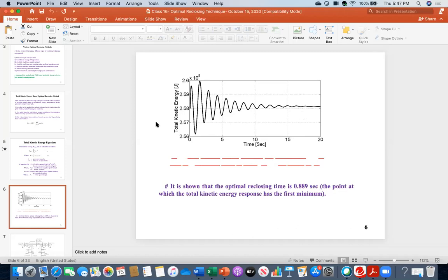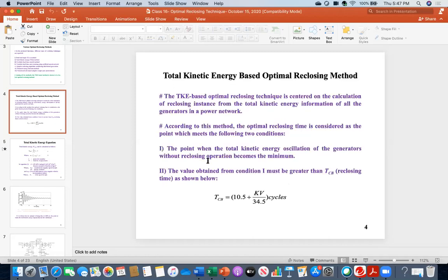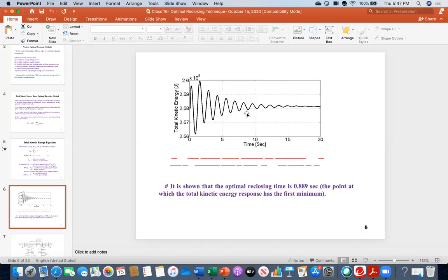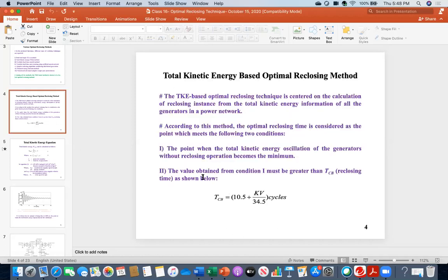Now, what is that optimal reclosing technique? Come back here and read the first point: the point when the total kinetic energy oscillation of the generators without reclosing operation becomes the minimum. So you have to look at the total kinetic energy curve and see which one is the minimum point. Now, the fault happened, the circuit breaker opened, and you did not reclose the circuit breaker. The condition is without reclosing operation, because you want to calculate the optimal reclosing instance. Still, you did not reclose the breaker. The fault happened, you captured all the information, and you calculated the total kinetic energy.